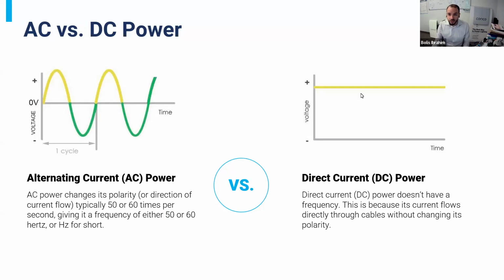That affords many benefits for direct current power, but a safety drawback. This is why alternating current initially won the war of the currents—it has zero crossings, crosses 0 volts, so it's safer to use with mechanical contacts. You can't use mechanical contacts with DC because there's no zero cross, so your arc energy is very high.